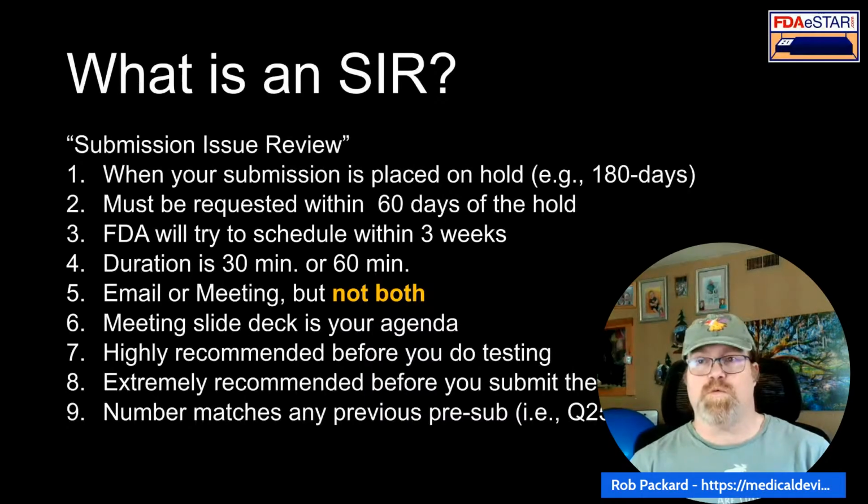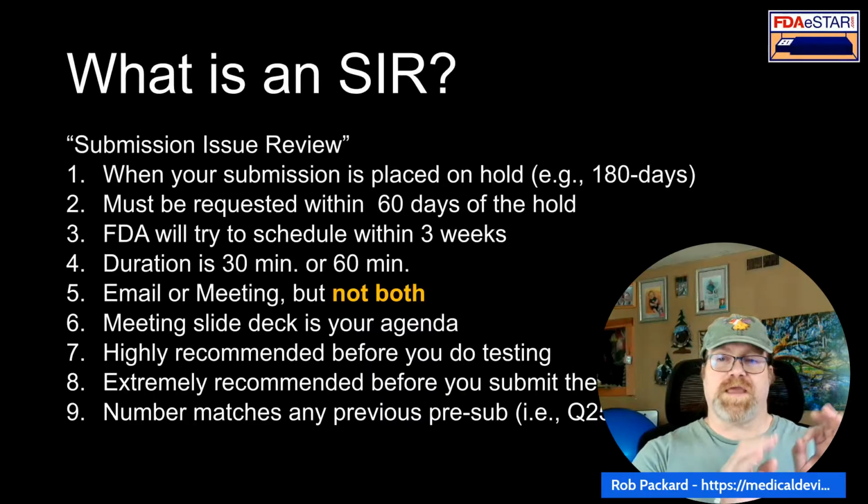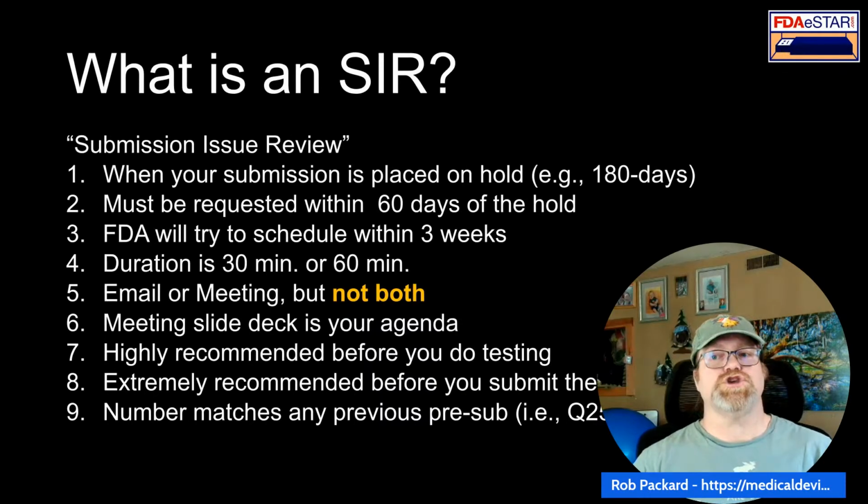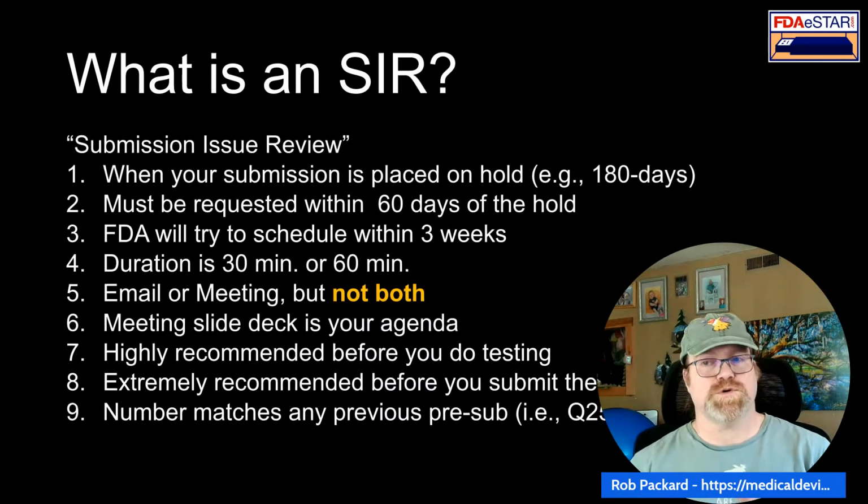Email or meeting, we already discussed this for the pre-subs, but for the SIR, you don't have both options. In a pre-sub, they send you the email response first, and then 5 days later, you have a meeting to discuss the email, and they give you the option of canceling the meeting if the email was sufficient. SIRs don't have that option. So it's either an email response from the FDA or a meeting. You cannot have both.